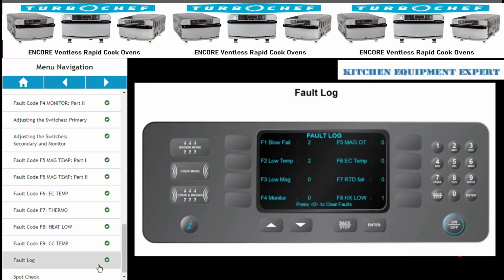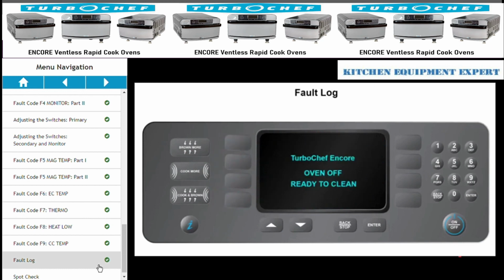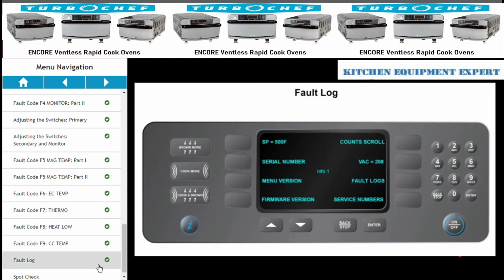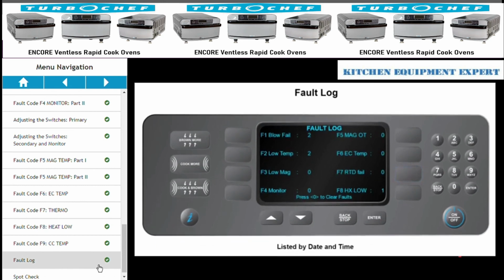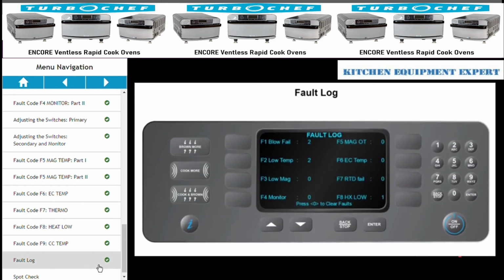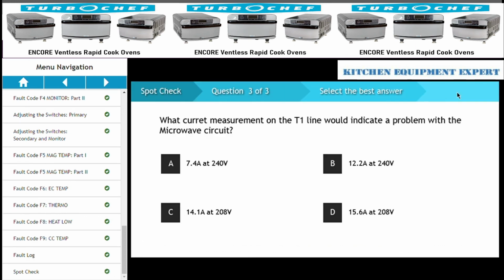The oven registers each fault code in its memory. To access the fault log, press the info key, and from the first screen, press the soft key next to the fault logs. Each fault code has all of the incidents listed by date and time of the occurrence. This history can help you put together a picture of what's going on with the oven.